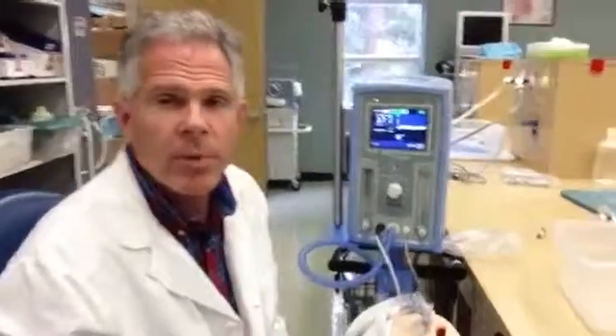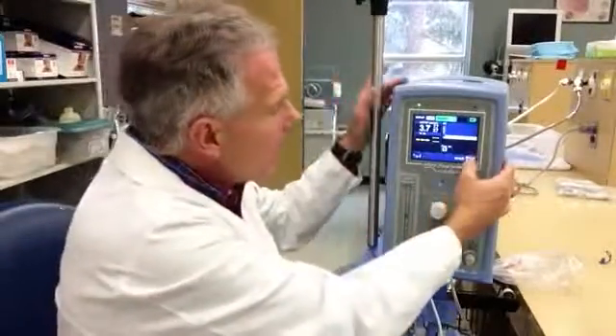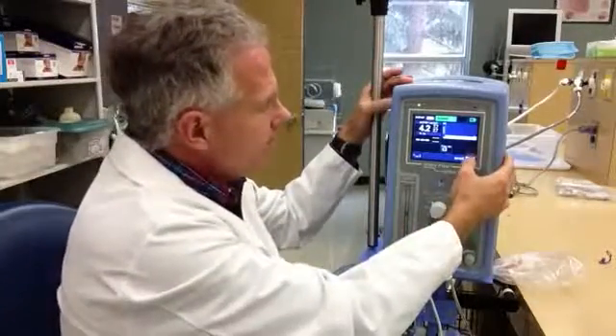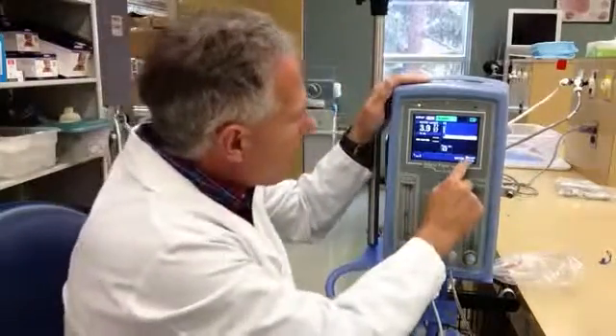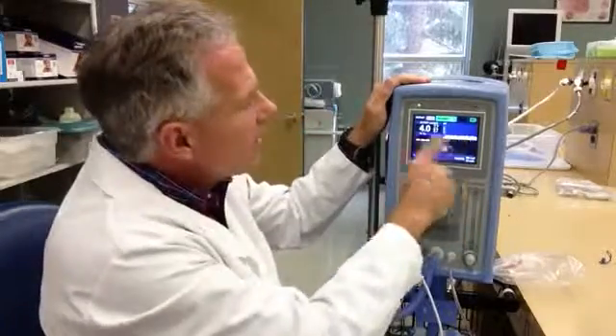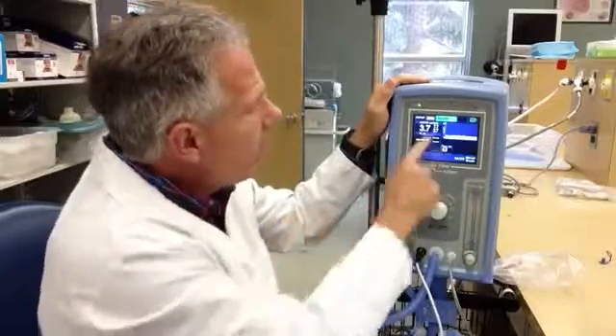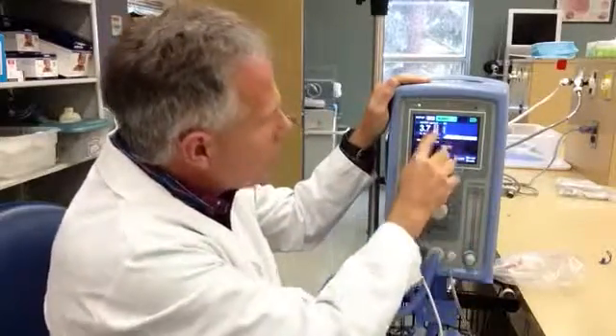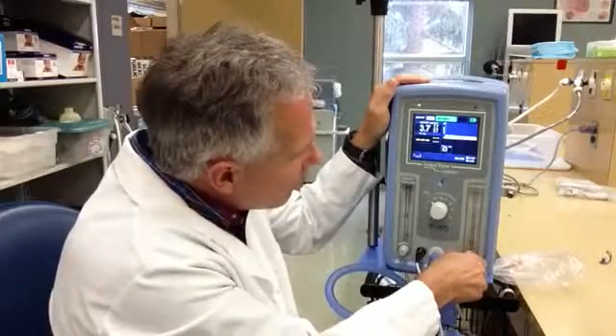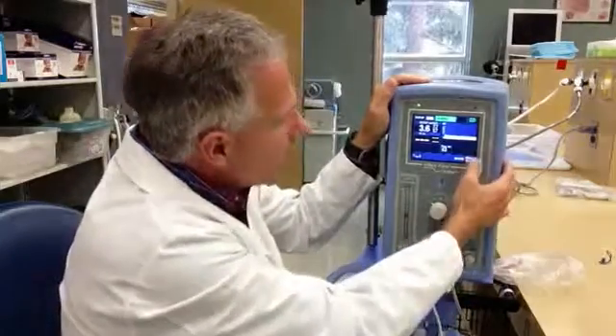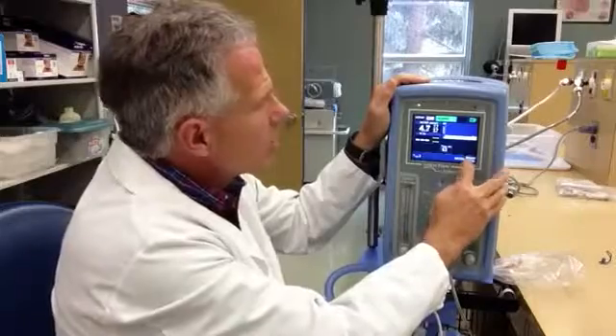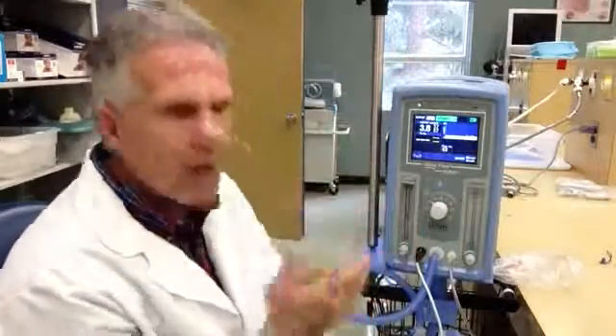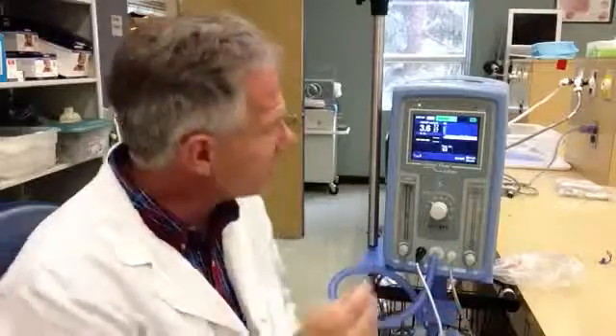One last thing I would mention about this ventilator: you do have the ability to give a manual breath. That manual breath will go to whatever pressures you had set on the high pressure here. It shows you what they are here, and shows you what your alarm limits are going to be. I can increase that a little bit by turning up that flow. So now I'm giving a little bit larger pressures for my manual breath. So that in a nutshell is the SiPAP neonatal infant ventilator, primarily used to deliver nasal CPAP.